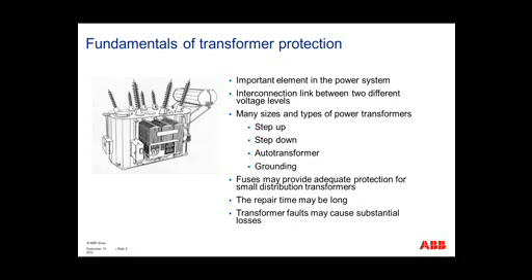Grounding transformers. If you're in need of a source for zero sequence grounding in the network, you can use a grounding transformer. Other transformers, you could have power reactors, to add reactance to the system if needed. You could have a phase angle transformer. A phase angle transformer controls the power flow of the system.